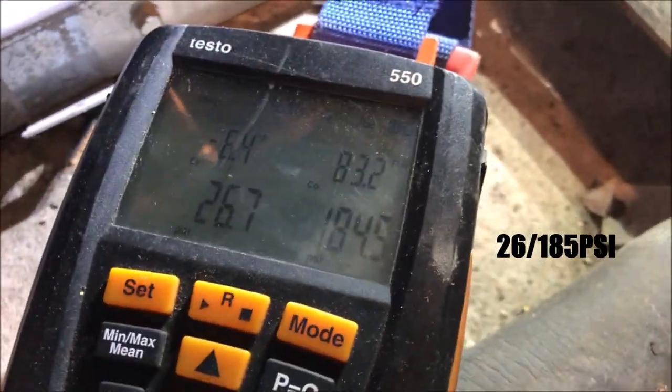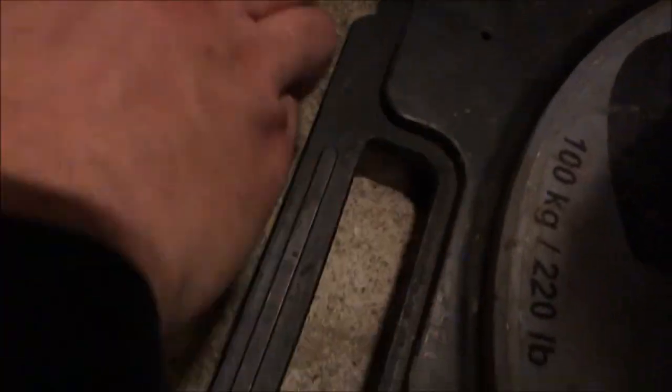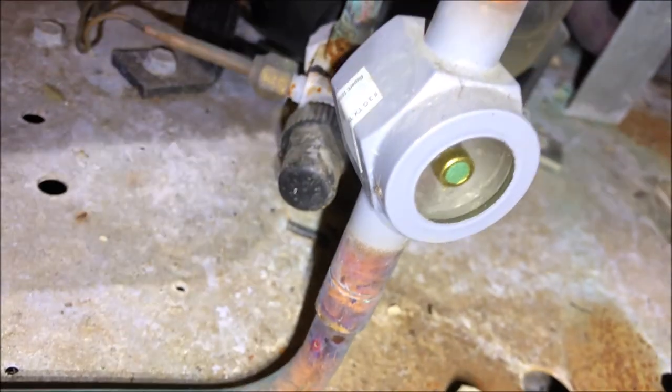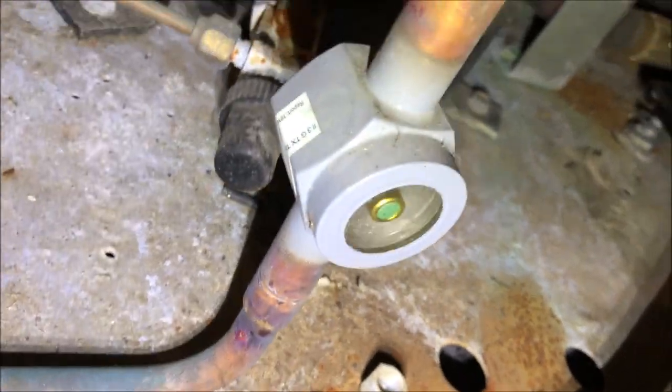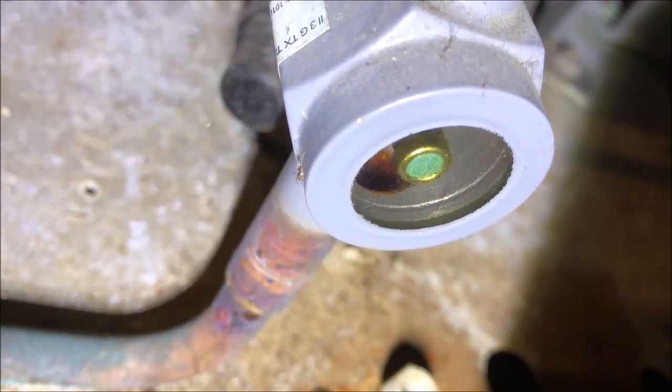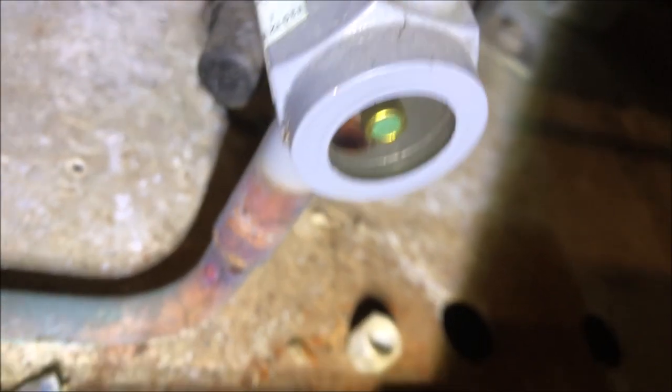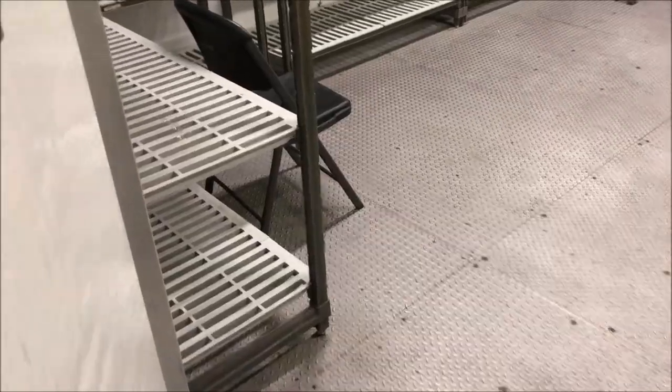So our pressures are 26 and 185. We've got about four and a half pounds in there. The sight glass is still flashing, so let's continue to charge it. We've got the sight glass full. All right, the sight glass is finally full. The pressures are up to 44 and 182, and you can see we're at temperature here, 35.